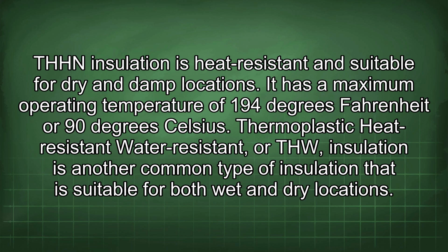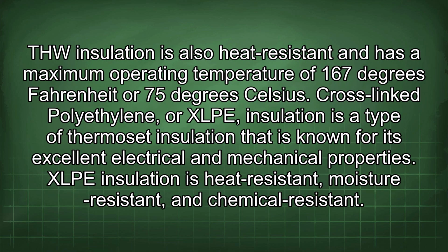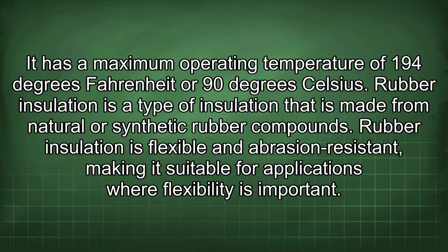It has a maximum operating temperature of 194 degrees Fahrenheit or 90 degrees Celsius. Thermoplastic heat resistant water resistant, or THW, insulation is another common type of insulation that is suitable for both wet and dry locations. THW insulation is also heat resistant and has a maximum operating temperature of 167 degrees Fahrenheit or 75 degrees Celsius. Cross-linked polyethylene, or XLPE, insulation is a type of thermoset insulation that is known for its excellent electrical and mechanical properties. XLPE insulation is heat resistant, moisture resistant, and chemical resistant. It has a maximum operating temperature of 194 degrees Fahrenheit or 90 degrees Celsius.